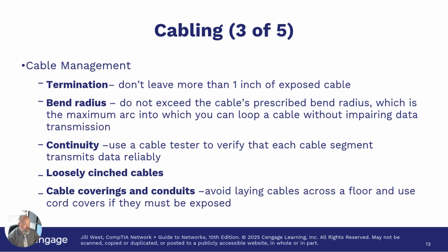So with cables comes cable management. Make sure that this is kind of like an art, actually, when you look at some of these systems in data rooms. Termination: make sure that you don't leave more than 1 inch of cable exposed. Too much exposed wire is like having your shirt untucked. Honestly, it looks sloppy and it can cause some problems.